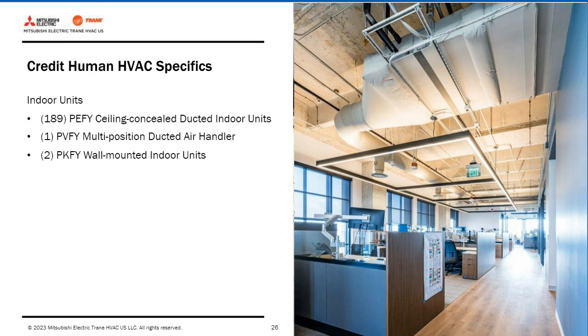So the interior of the building is served by a VRF system. The majority of the units are exposed. You can see that in some of the pictures in earlier slides and this picture. There's a couple of ductless wall-mounted units, like in back of house areas, but most of it is these ceiling-hung fan coil units that you can see at the middle of this slide with the black refrigerant pipes running to it above this desk.